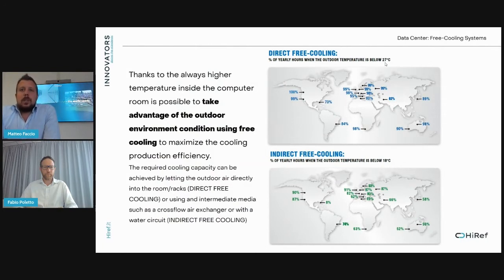We can use free cooling in a direct way, so we can bring external air directly into the room, or we can use free cooling in an indirect way, so we can use an intermediate medium such as a cross-flow heat exchanger or a water loop to take advantage of the free cooling.